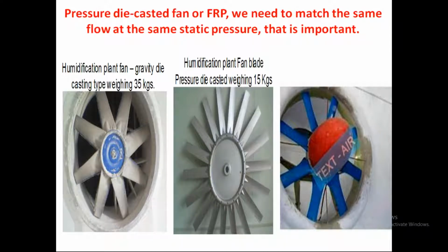But what is the problem with all the textile mills and the OEMs is they measure only the flow. If you measure the static pressure, are you maintaining the same 30,000 CFM at 600 Pascal before and after? If you are able to measure the Pascal before and after, then you are 100% convinced that the energy savings are achieved. So kindly confirm this, please.